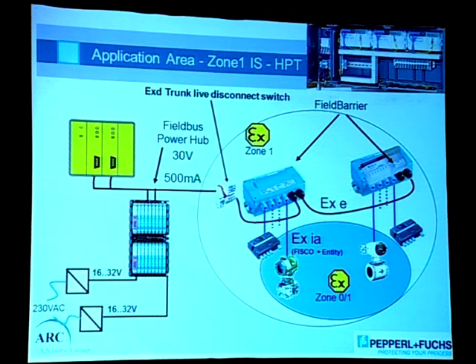This is the method we call the high power trunk, officially recognized by Foundation Fieldbus and other types of Fieldbus like Profibus. What we do is not do the intrinsic safety in the power supply. That is the biggest problem, because it limits the voltage and the current. Instead, we allow higher voltage and higher current, and we bring the energy to the junction box, where we have safety barriers inside, and they do the limitation. By doing so, we eliminate all the limitations like voltage, higher power, and redundancy, and we build the diagnostics on board. Other practical problems are all eliminated as well. So this meets almost the entire requirement of intrinsic safety for hazardous area applications. But one of the main limitations here is that the trunk line we bring from the control room all the way to the field is not intrinsically safe.